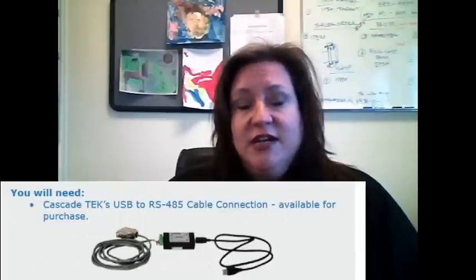This video is going to help you get started using our TFO or TVO ovens with the standard RS-485 communications and the free Watlow configurator software. In order to use the standard communications and the Watlow configurator software, you're going to need to have an RS-485 to USB converter cable. You can make your own, just give me a call, I'll tell you about the pinouts and give you the wiring schematic, or you can purchase one from us as an accessory.